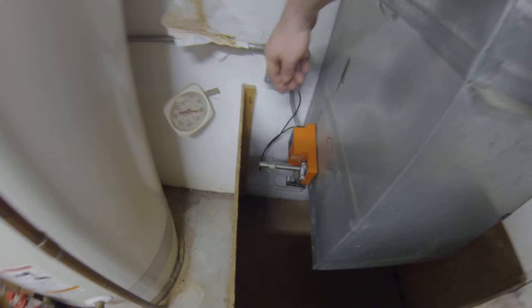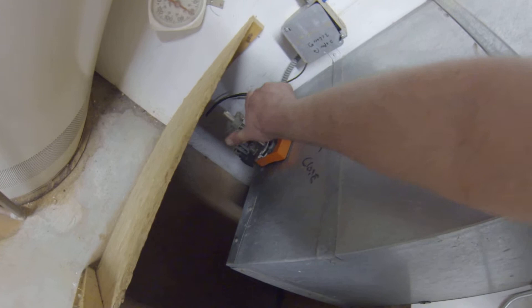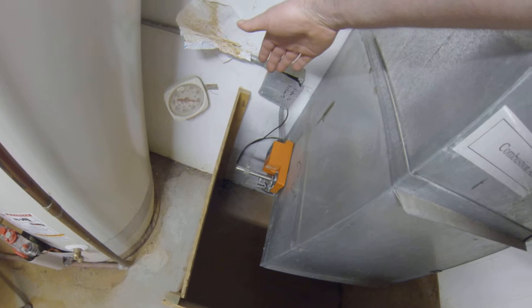If we didn't do that, if we held in the manual release switch and pushed the damper open, if that relay were in place the motor would be trying to close itself. But we want to open it manually and by pulling the relay it will stay put now. I feel fresh air coming in. Now we're ready to fire the boiler.